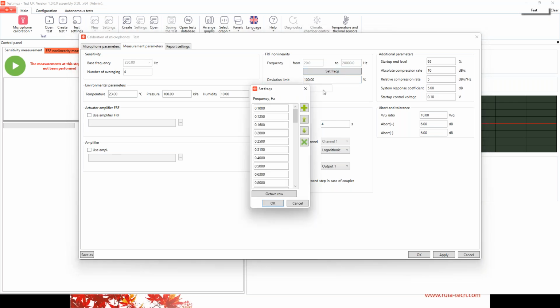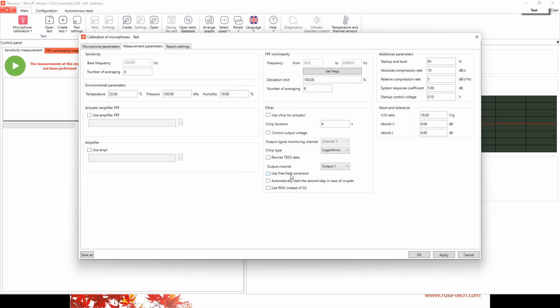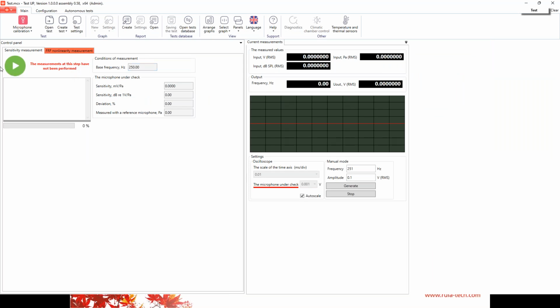Here you see set of frequencies. Here we see the main third of an octave row, but I want to make it less, so let's enter 100 Hertz and 1000 Hertz. Here you see our frequencies. Here we enter the deviation limit and the number of averaging. Our first calibration will be done with the regular sine signal, so we don't enable sine chirp for actuator. And now I think we can start. Let's press start button.